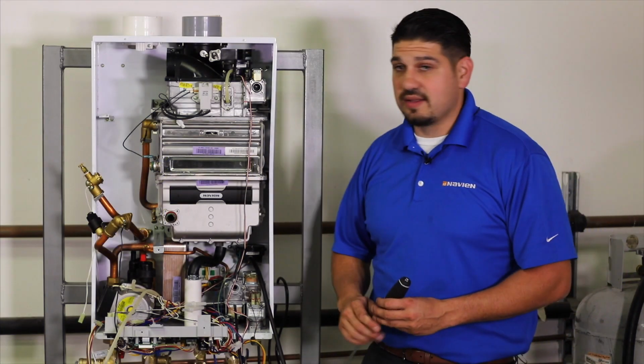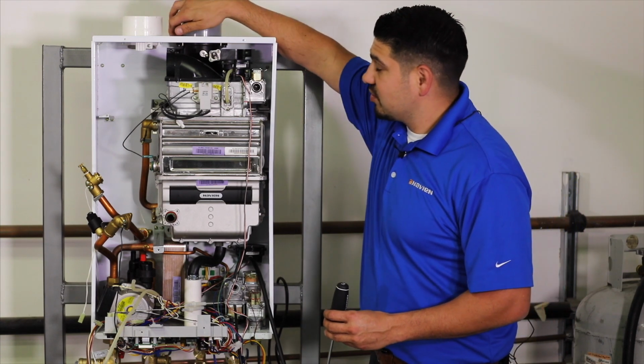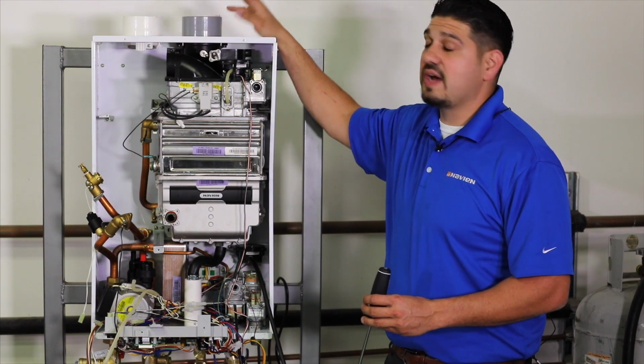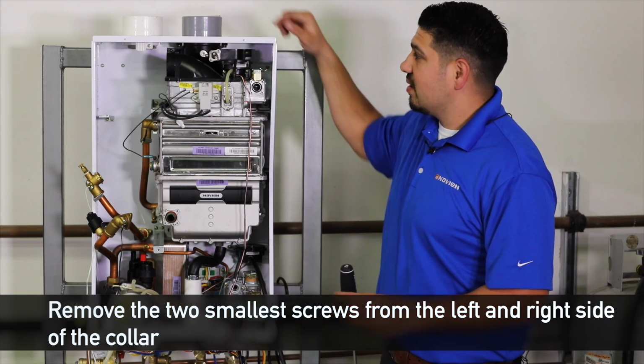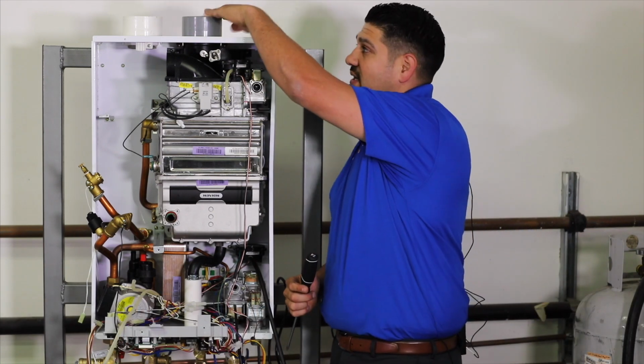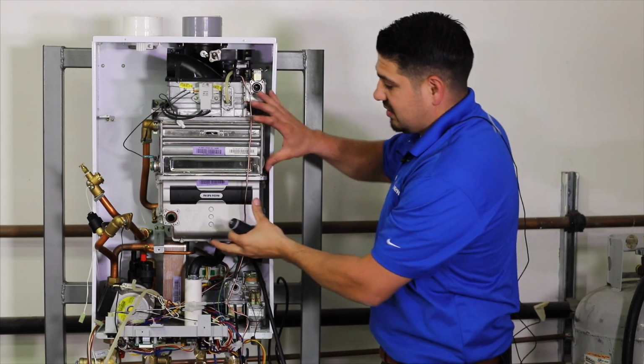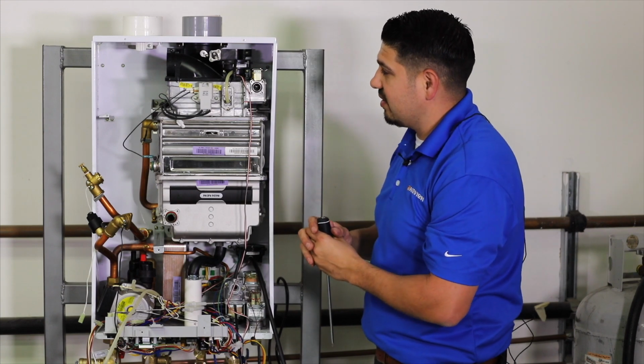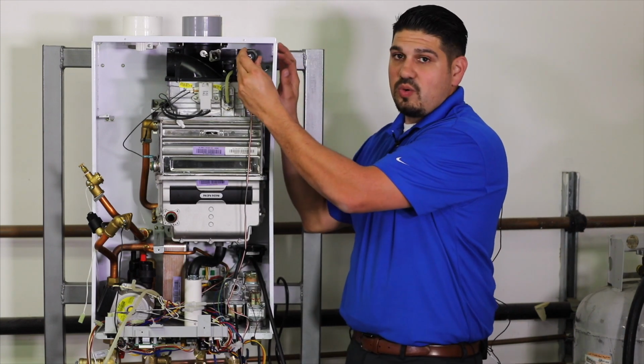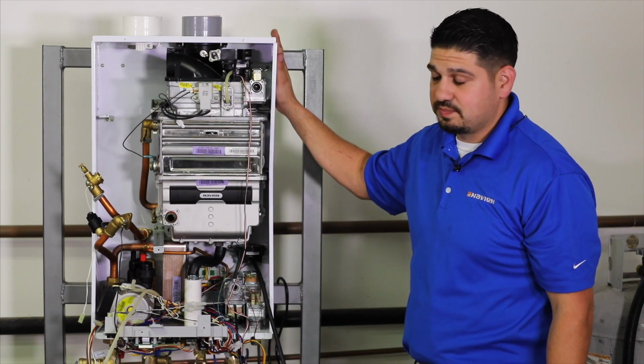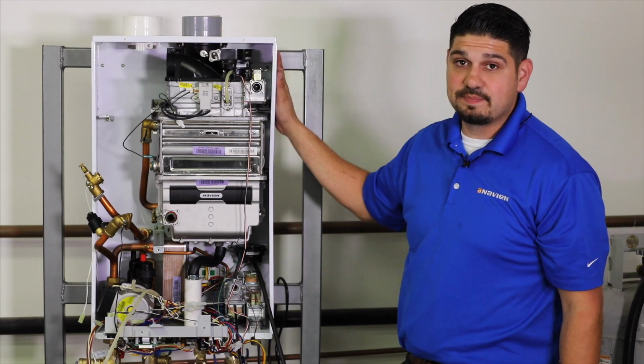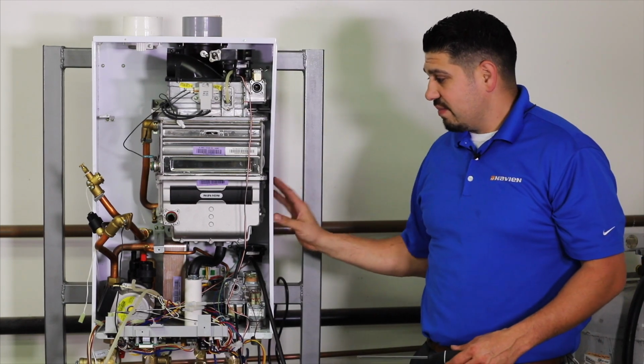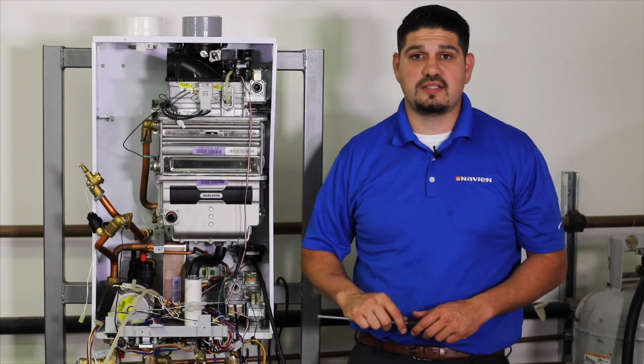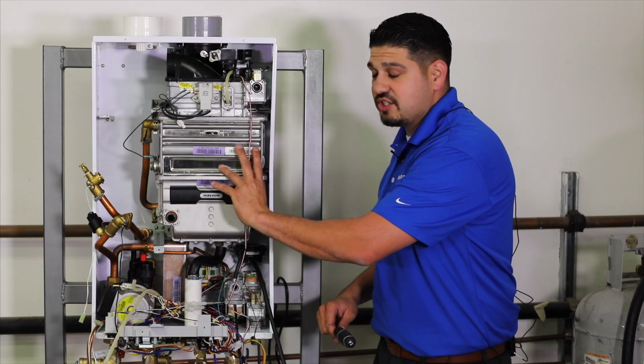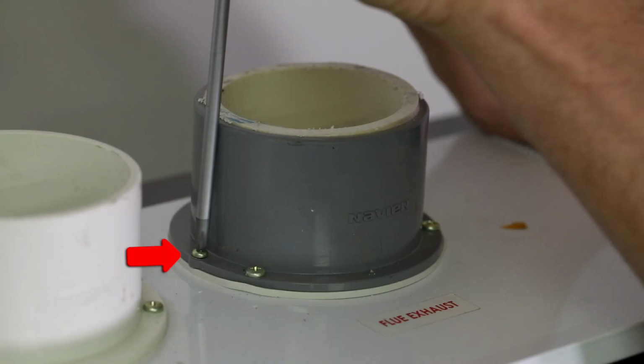We're just about ready to pull this thing out of there. What we need to do, there's actually a total of 5 screws holding this collar on here, but the ones we're mainly interested in are the 2 small ones on the very top. We're going to unscrew those, which is going to release the collar from the exhaust duct. This heat exchanger is connected to the exhaust duct, so we need to separate those. There's also, right here in this upper corner, a single screw that's connecting the exhaust duct to the cabinet, and there are 4 mounting brackets on both the right and left hand side of this unit with anywhere from 1 to 2 screws holding this assembly to the cabinet.